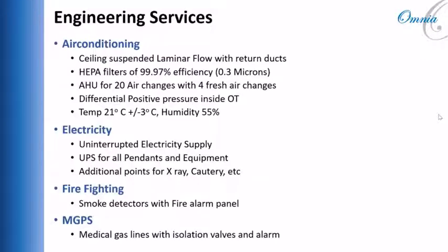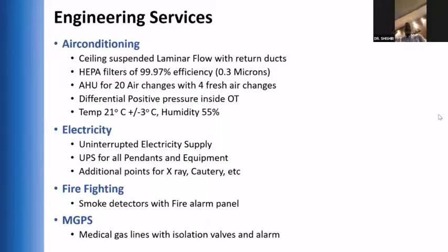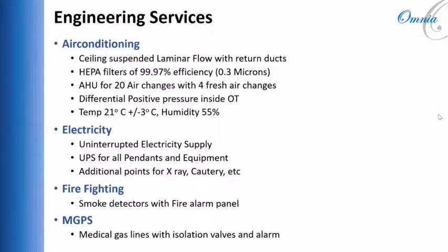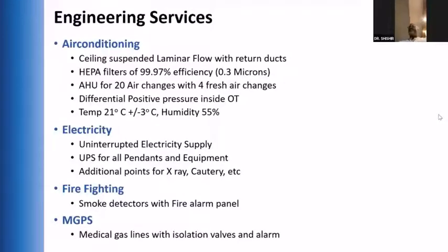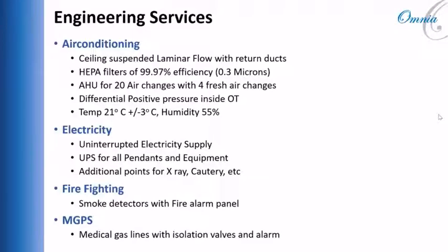There should be a differential positive pressure inside the OT. That means the outside corridor should be at lower pressure than the OT area. Temperature inside the OT should be 21 degrees plus or minus 3 degrees Celsius. Humidity should be 55%. Then electricity, obviously we agree that uninterrupted electrical supply should be there, but all pendants and equipment should come with UPS. Also, even if it is not written here, we have to ensure that there is additional earthing provided for all the OTs. Additional points should be considered for cautery, X-ray, and for laser cautery, obviously differently.